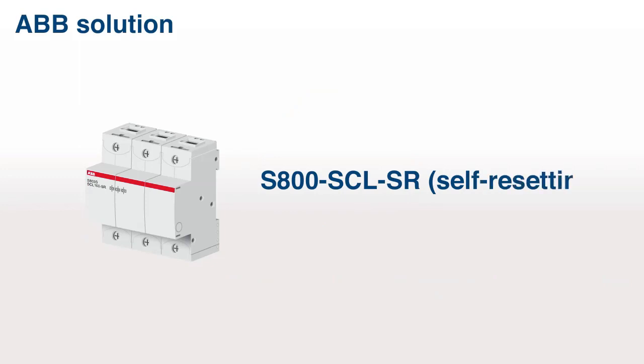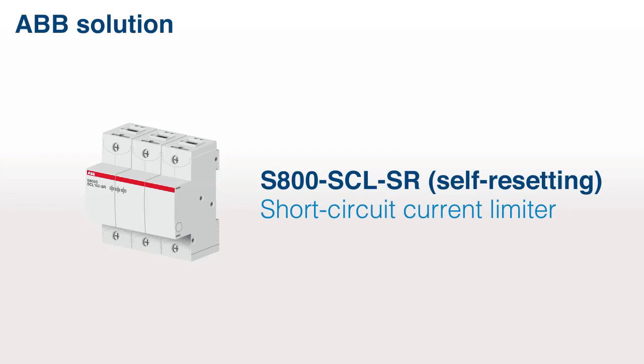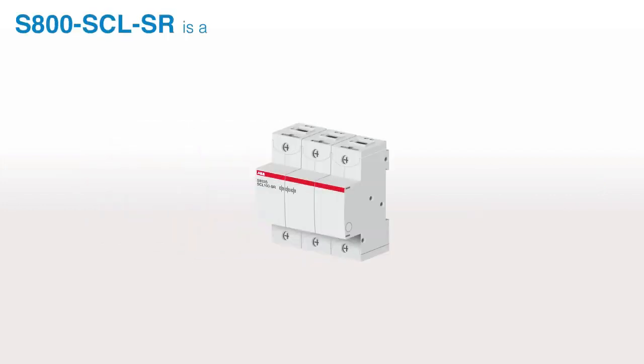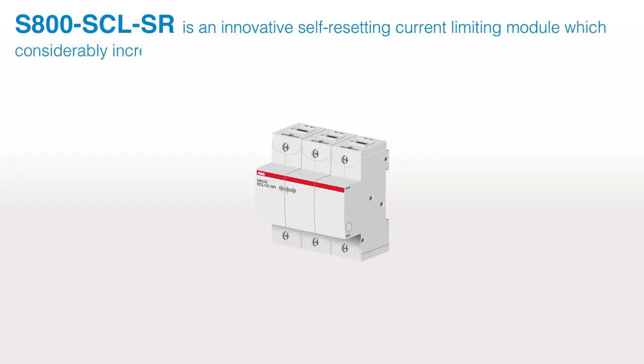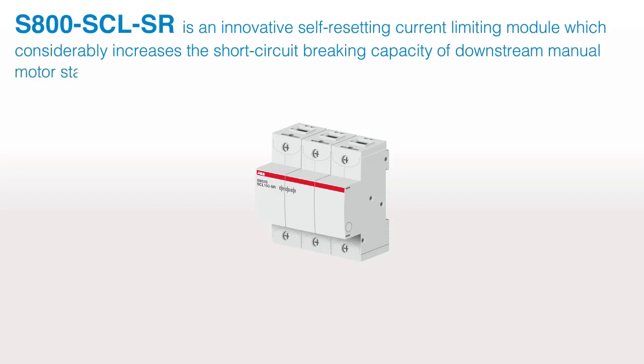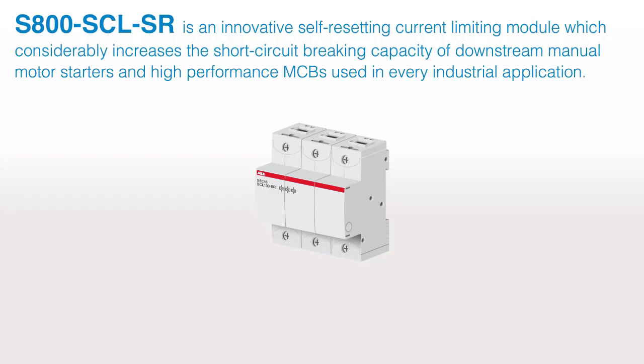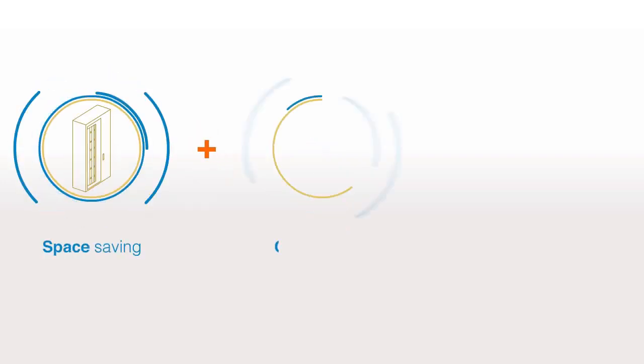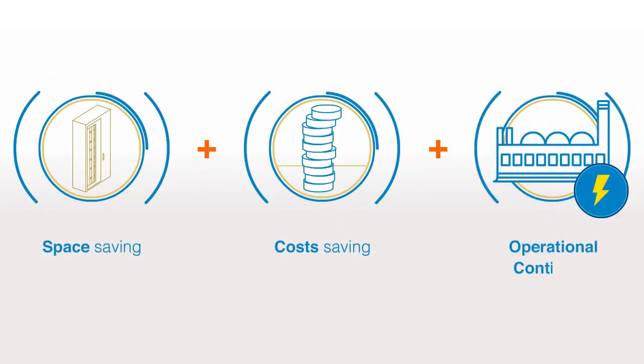ABB's solution: S800 SCL SR Self-Resetting Short Circuit Current Limiter. S800 SCL SR is an innovative self-resetting current limiting module which considerably increases the short-circuit breaking capacity of downstream manual motor starters and high-performance MCBs used in every industrial application. Space saving, cost saving, operational continuity.